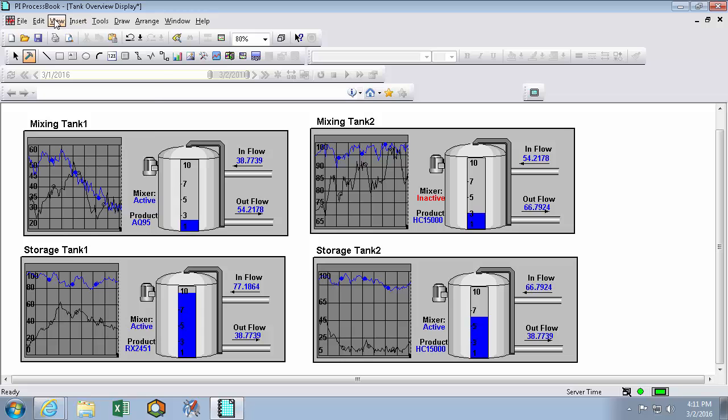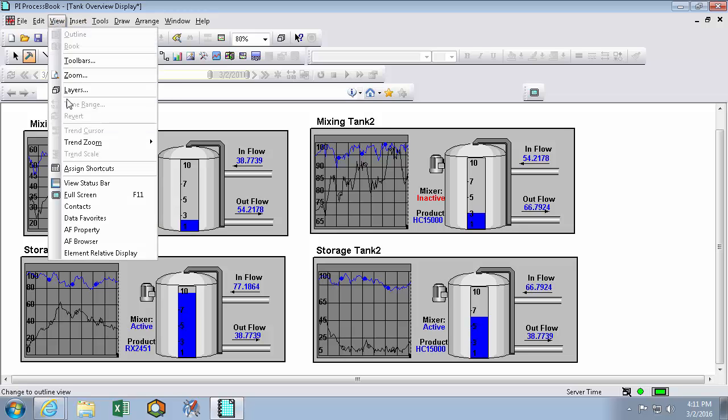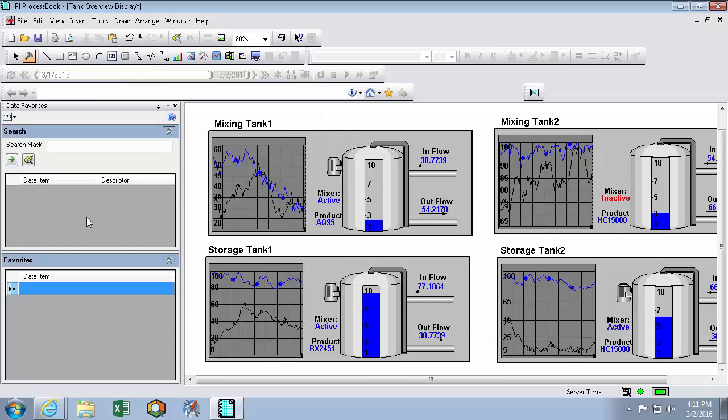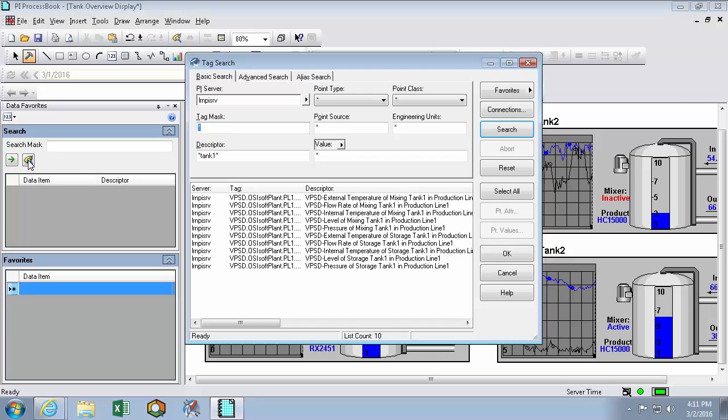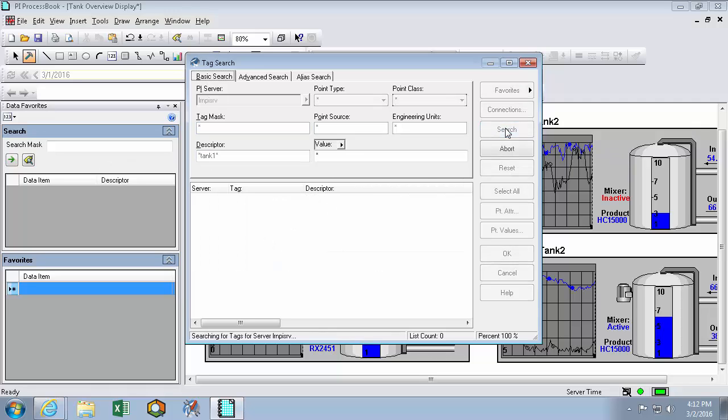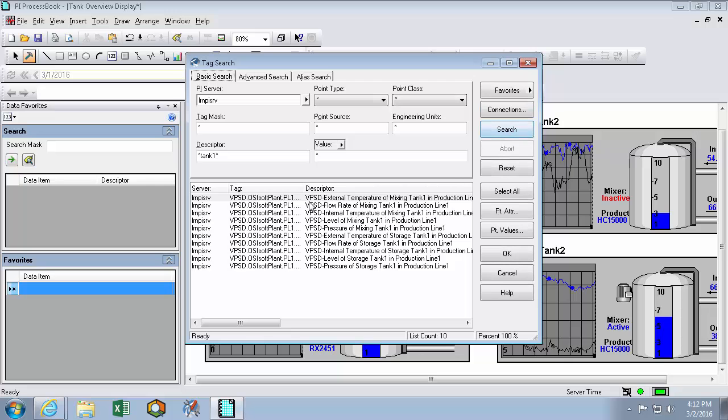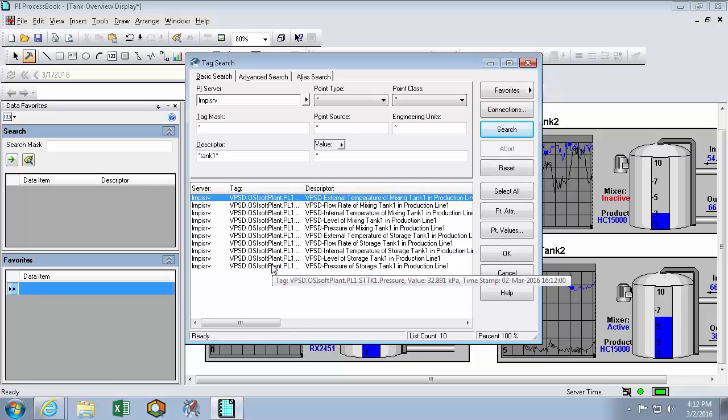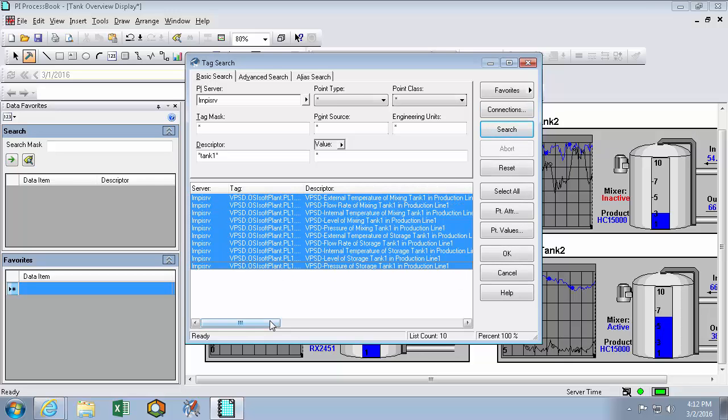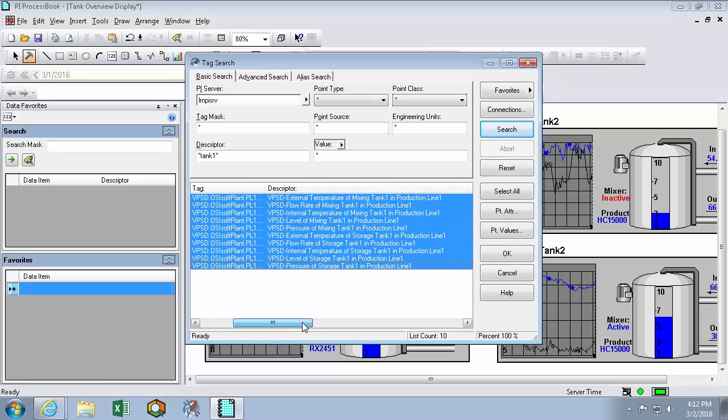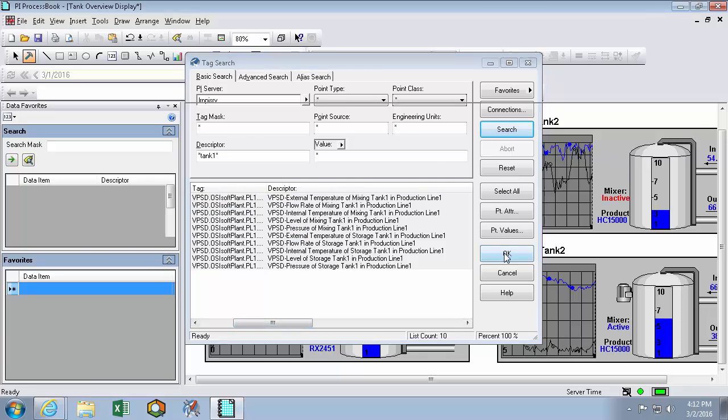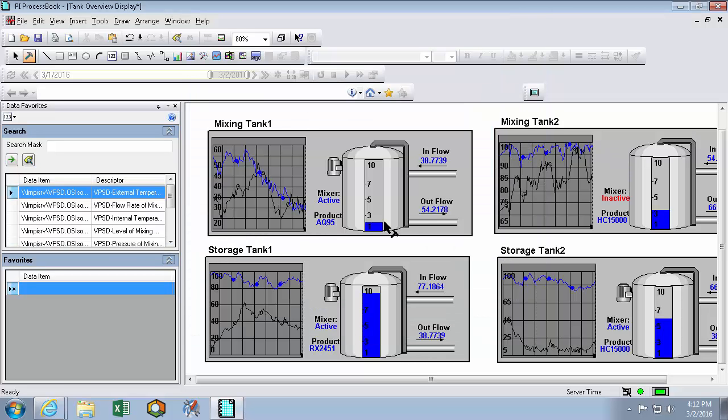So here in view data favorites, we can search for PI Points directly. So what I'll do is search for anything with tank 1 in the descriptor. This will produce my 10 PI Points associated with tank 1. So I'll hit OK. And they'll appear in the search results window.